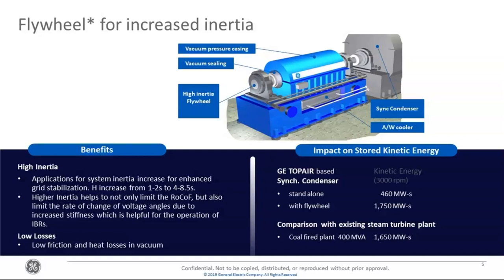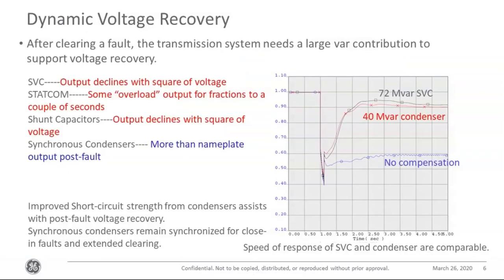Okay. The next aspect is dynamic voltage recovery. Now, after a fault is cleared, the transmission system needs a large amount of reactive power contribution to recover from the low voltage condition. Now, shunt caps and also SVCs, once they run into their limits, have a reactive power output that is directly proportional to the square of the voltage magnitude. So when you are in low voltage conditions, the reactive contribution of these devices is further reduced, which can be an issue, which makes it difficult for the voltage to recover, especially in weak grids where you may have a higher percentage of motor loads that are prone to stalling. This becomes an even bigger issue.